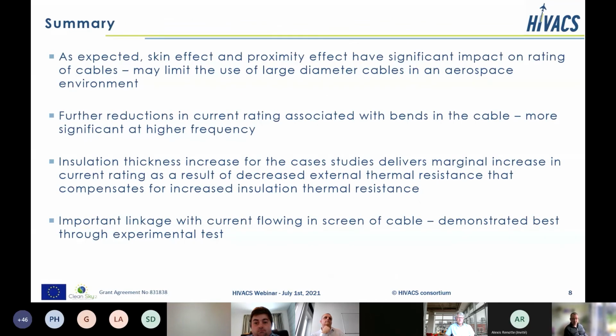So within the modeling, we've seen skin effect and proximity effect definitely having a significant impact on the rating of the cables. And what this really means is large diameter cables may well not be preferred, because if you keep on adding diameter to your conductor, but that conductor is not used as a consequence of the skin effect, then why add it? You're just adding weight for no value. It is important to look at the current rating associated with bends, and these can be more significant at high frequency.